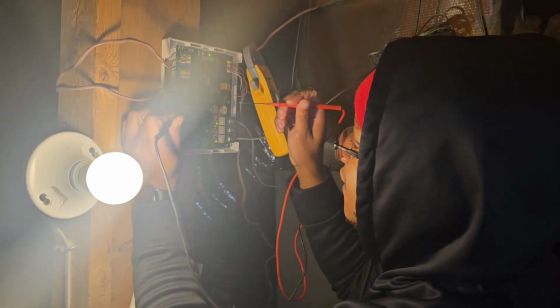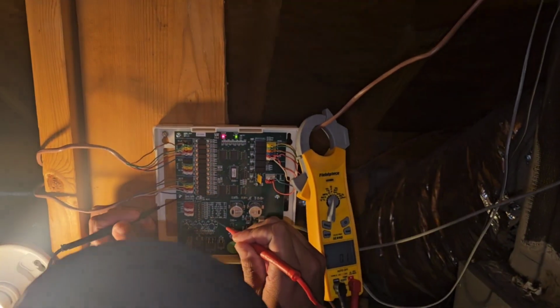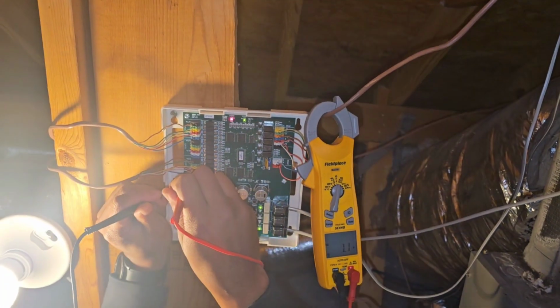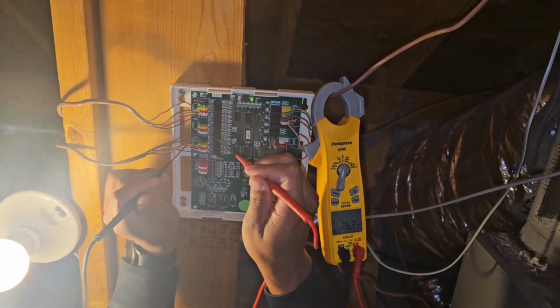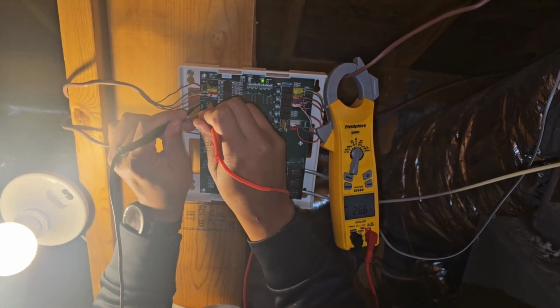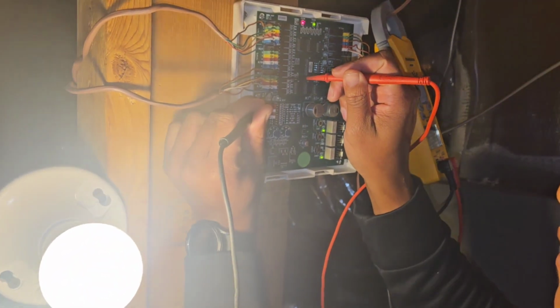Let's make sure we got 24 volts going to each thermostat. Common there. R, 26 volts. Common. R, 26 volts. Okay, so do I have the call for heat on both of these?